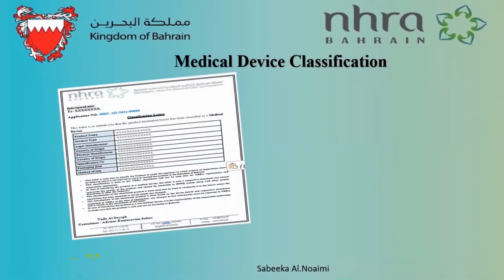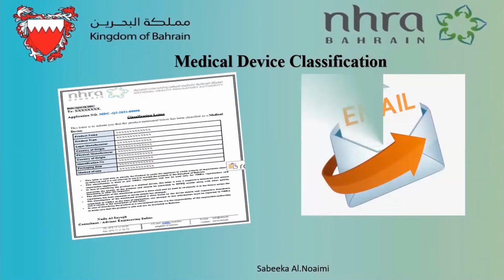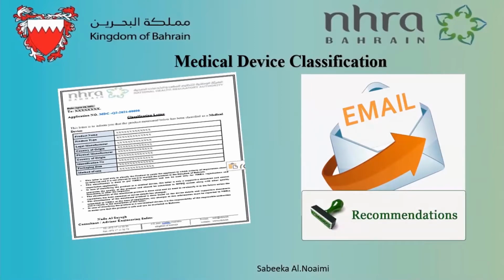In case the product is classified as a medical device, the applicant will receive a classification letter to be used for every importation request. In case the product is not classified as a medical device, an email will be sent to the applicant clarifying the reason for the non-classification. Also, in case there is any missing document, an email will be sent to the applicant with recommendations, if any.